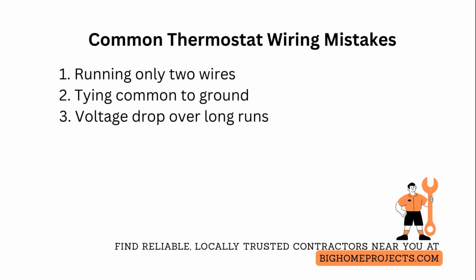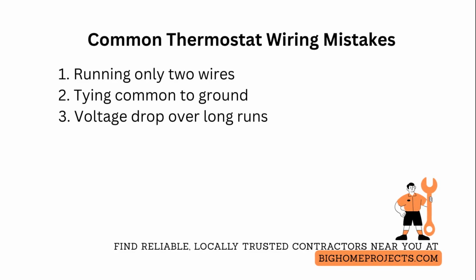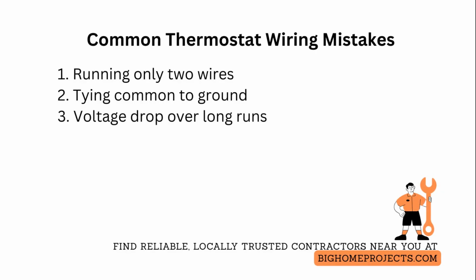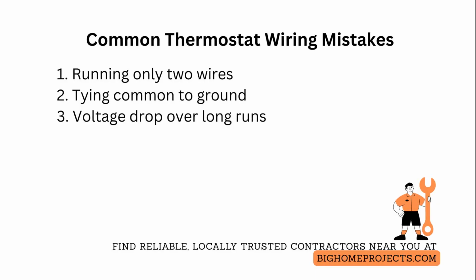One of the most common thermostat wiring mistakes is running exactly 2 wires and later discovering the condensing unit or smart thermostat needs a third. Fix this by pulling 3-conductor cable up front and labeling the extra wire as common or spare.